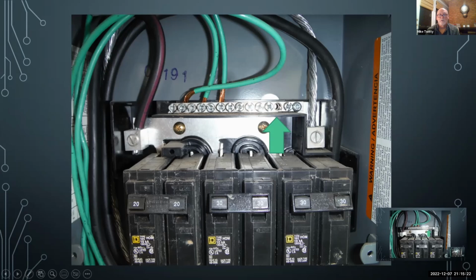This even has the little silver tape back there showing you where it goes. This is a tapped hole through here. That green screw we took out of that other sub panel, we put in our pocket. Now we're going to put it in here because we didn't have one. We're going to fix this. So look at this. This is a very common problem with HVAC sub panels. When they use a little sub panel for the HVAC equipment, and I'll pick on the HVAC guys a little bit, they're terrible about not bonding that bar.